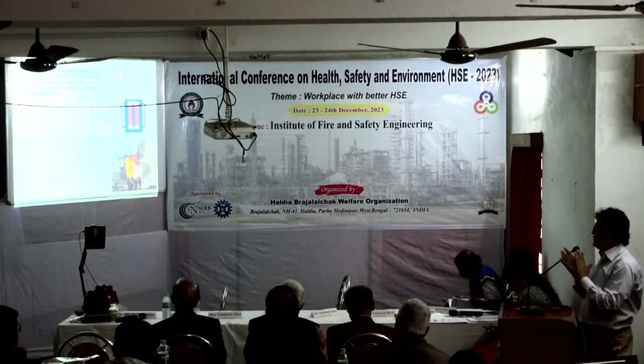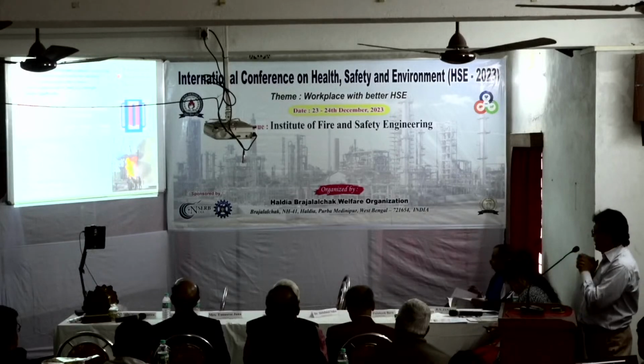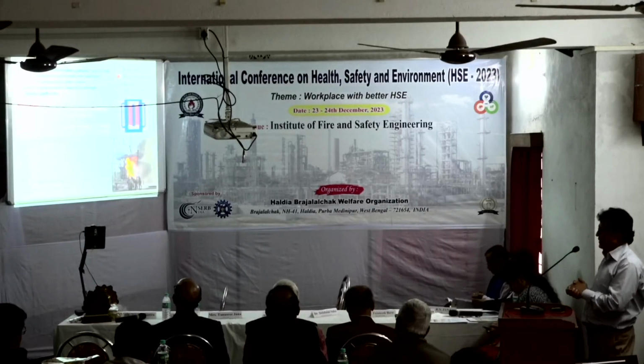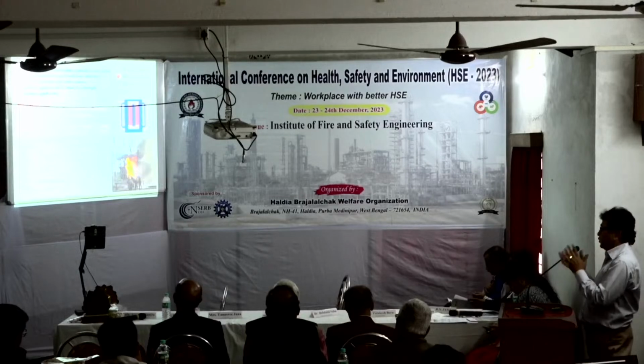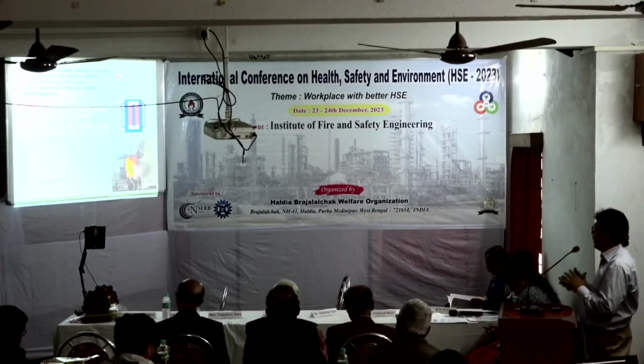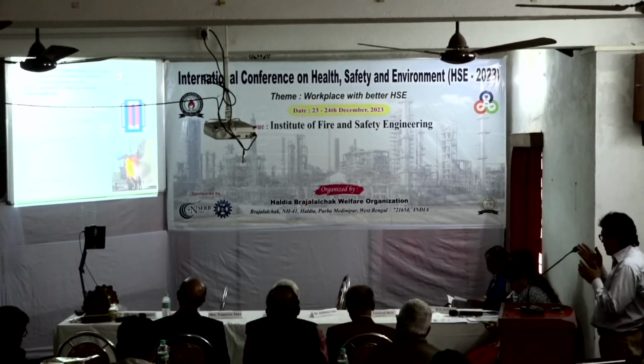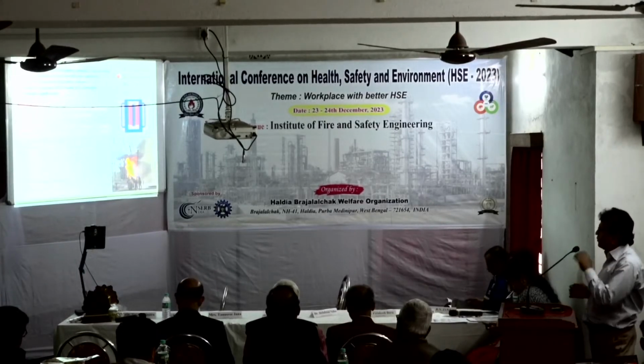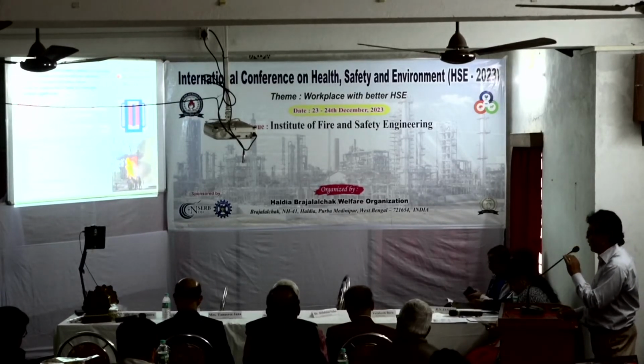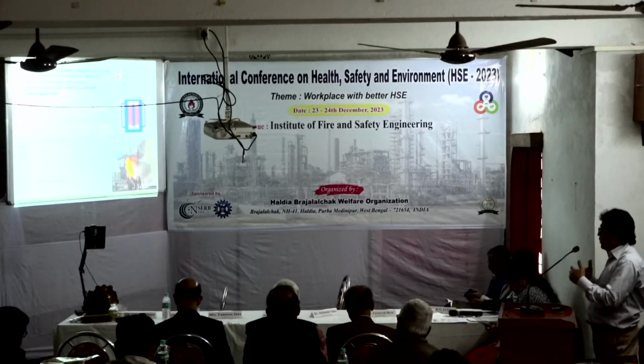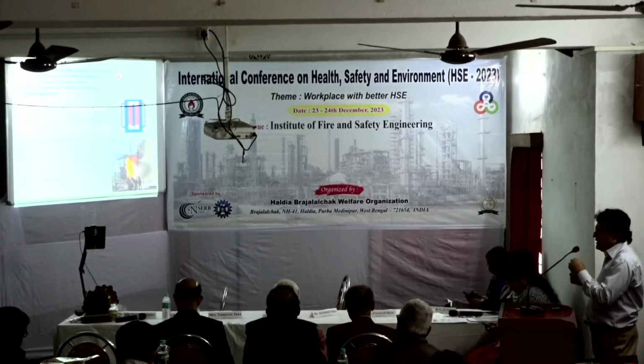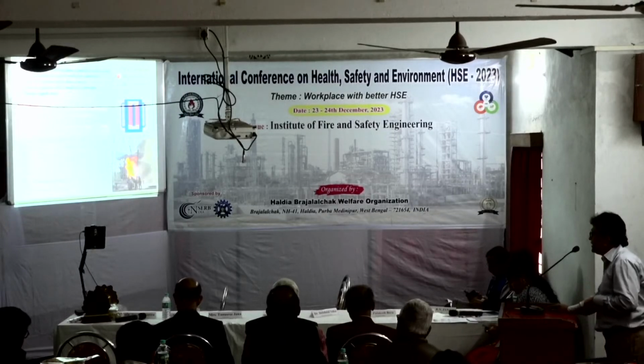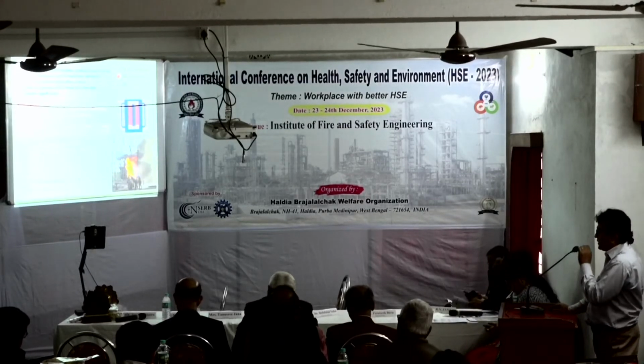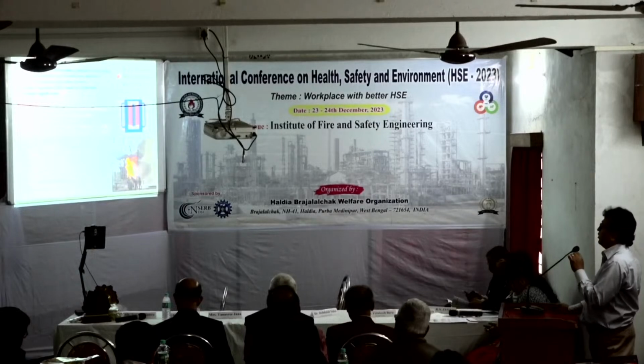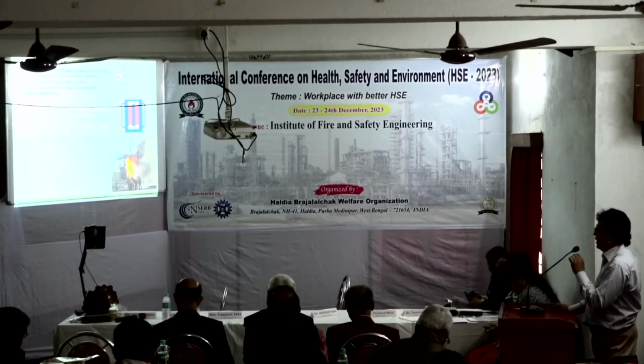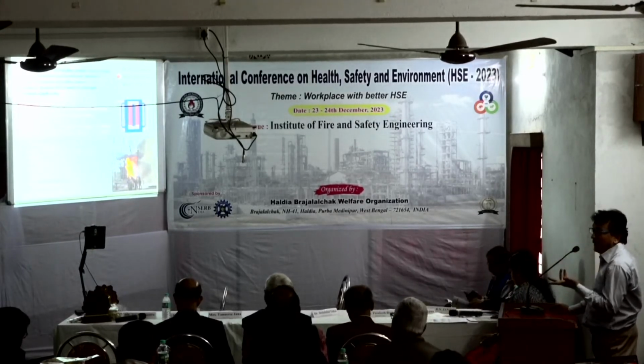In transformer oil, the dielectric breakdown voltage depends on the moisture content. Sometimes we see transformers bursting on the roadside. Why does a transformer burst? Because of slow weathering of the transformer, moisture leaks inside the dielectric oil, and more water reabsorption inside the oil brings down the dielectric breakdown voltage. As a result, when the moisture content is more than 30 or 40 ppm inside the dielectric oil of the transformer, a transformer accident takes place.